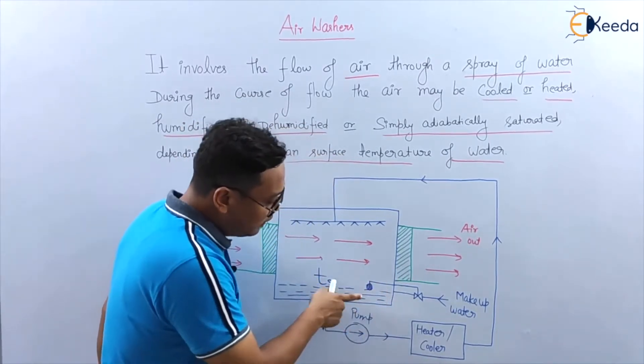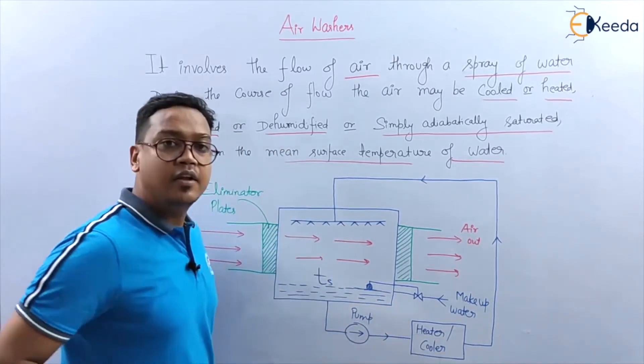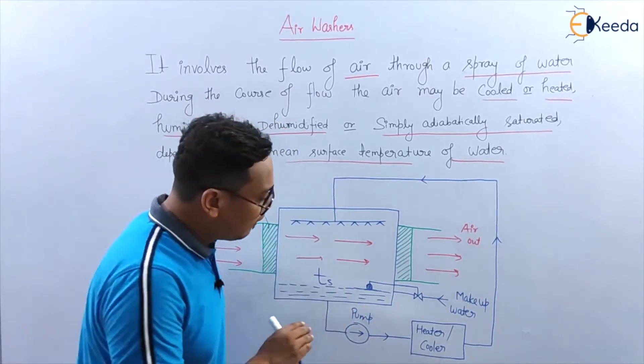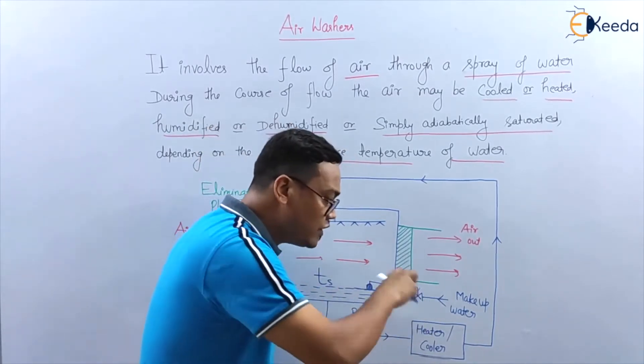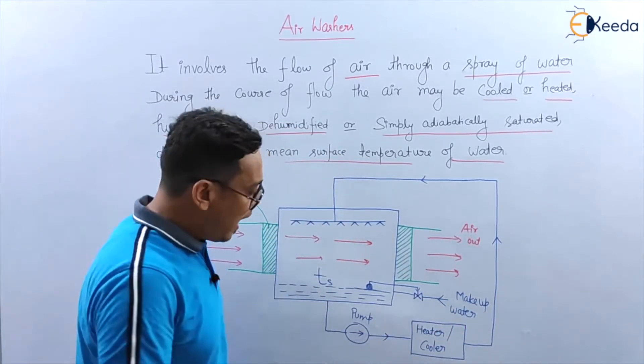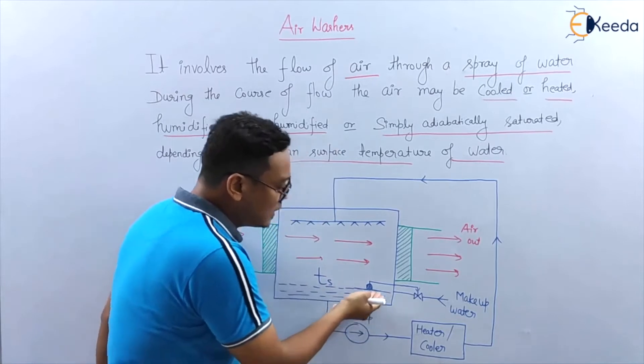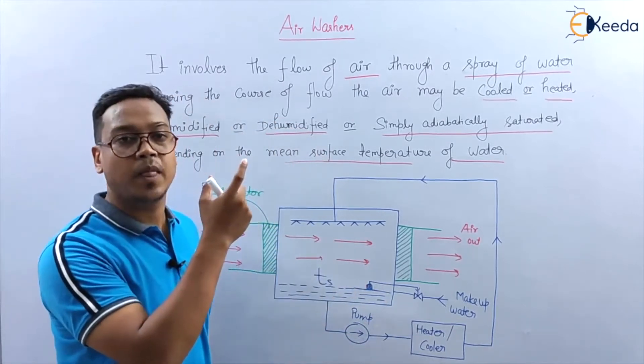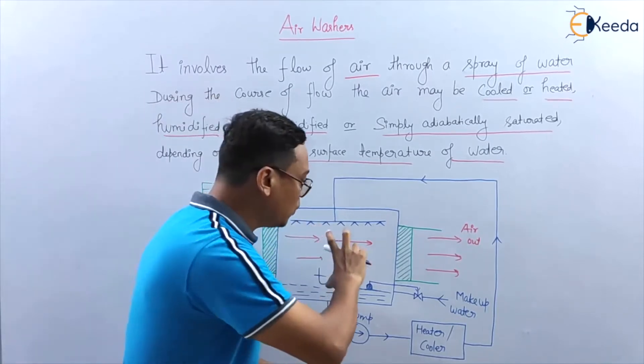If the water level goes down, this level indicator will sense the level of water and open this valve. As the valve is opened, makeup water will go into the air washer and the water level will rise. When the level is restored, the valve will close. By this makeup water line, we can add water to the air washer.